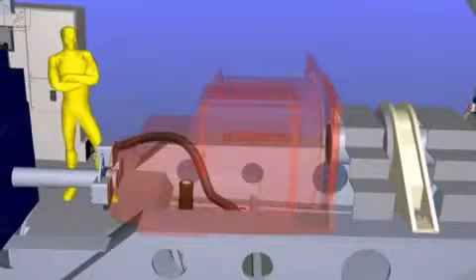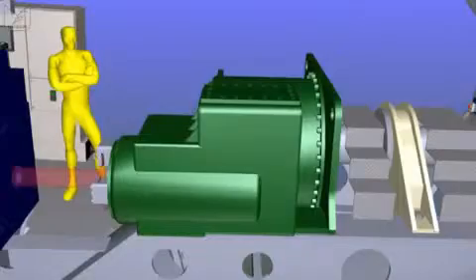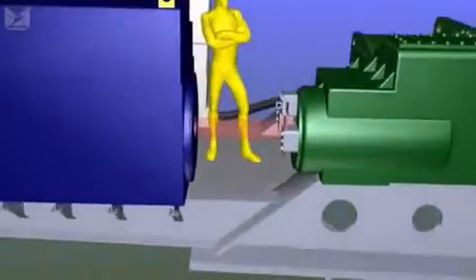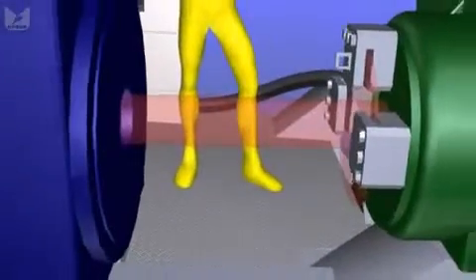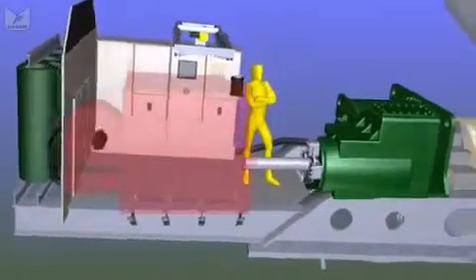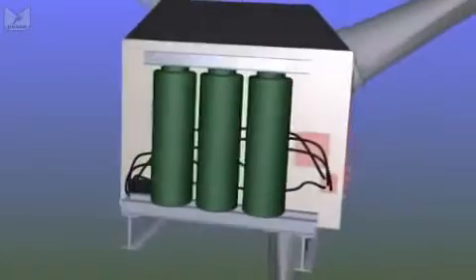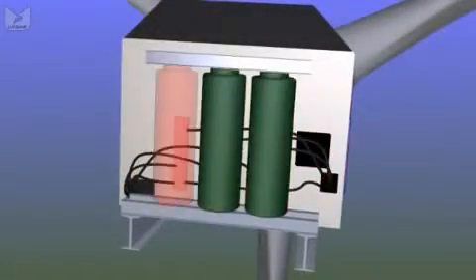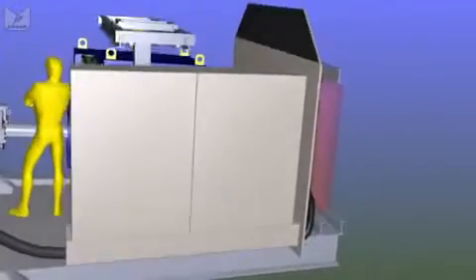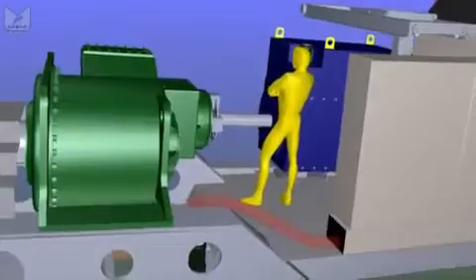So our main shaft drives our gearbox, which is mounted centrally because it's often the heaviest component. Out of the back comes a high speed shaft, as before, that's where the braking system is. High speed shaft then drives the generator, which is usually oil filled. The generator then supplies 690 volts, in this case into our transformer, which is sitting right next to it. That high voltage signal then passes through the switch gear and the cabinet, down the dropper cable, straight down to the bottom of the tower, through those switches on platform 2 and off to the substation.